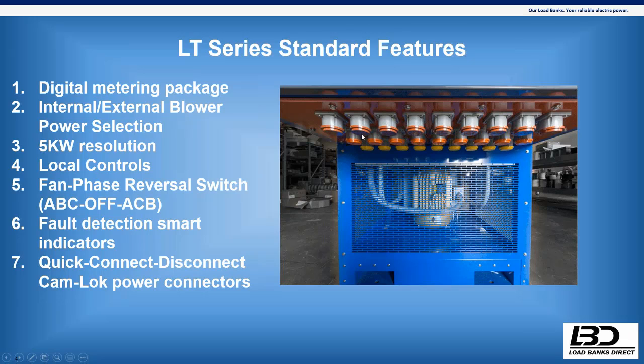All your quick connections also have spring-loaded covers. So say you're doing a load test and not using the full capacity of the load bank — you're only using half the Camlocks because you know you won't be drawing that many amps — those spring-loaded covers stay closed, so nobody has the ability to walk up and stick their finger in there and electrocute themselves. That's another standard feature we use for all of our Camlock quick connections.